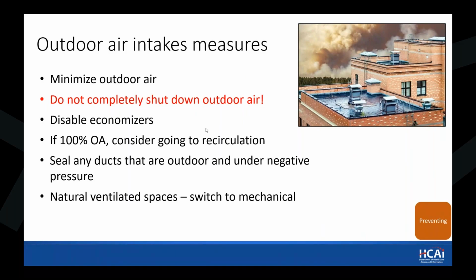You want to minimize certain sequences and operations within your HVAC system that would increase outside air intake, such as economizing modes. In some situations, healthcare facilities have 100% outside air HVAC systems, which are particularly challenged in this sort of event. Having a plan for how to operate in a more recirculating fashion is certainly easier in a new design when it's thought out and planned for versus a retrofit. But it's something to think about, especially for new facilities in areas of specific fire or smoke danger, to weigh against other factors when choosing 100% outside air systems.